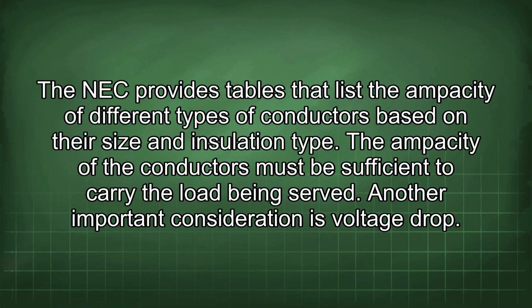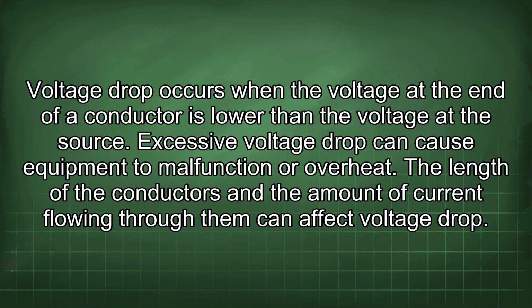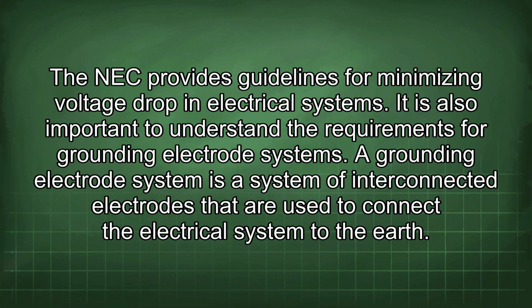Another important consideration is voltage drop. Voltage drop occurs when the voltage at the end of a conductor is lower than the voltage at the source. Excessive voltage drop can cause equipment to malfunction or overheat. The length of the conductors and the amount of current flowing through them can affect voltage drop. The NEC provides guidelines for minimizing voltage drop in electrical systems.